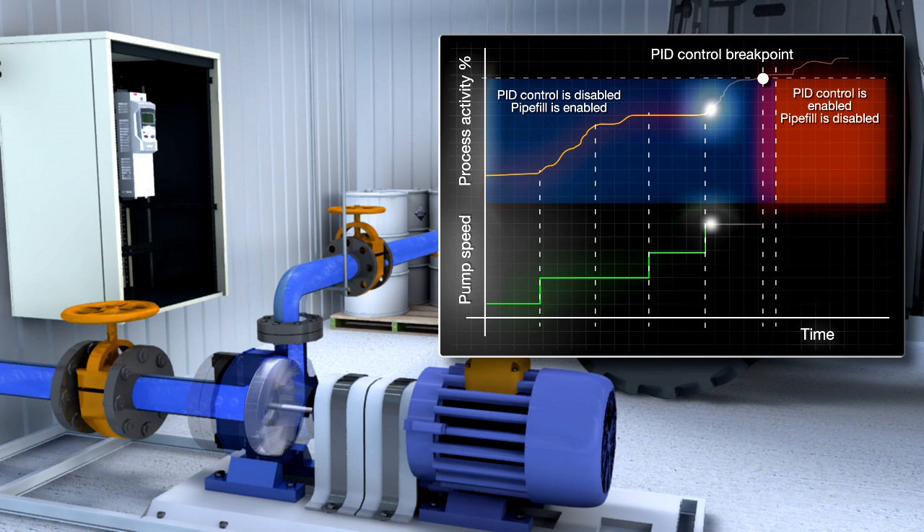When the pressure gets near to the final set point, the drive itself enables the PID control. The drive uses measured pressure or Pipefill's setpoint ramp-up function, whichever is optimum for the application.